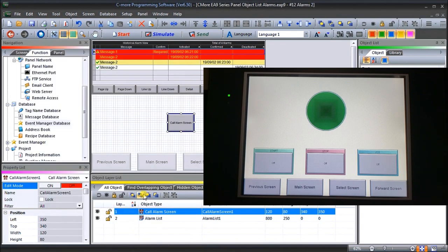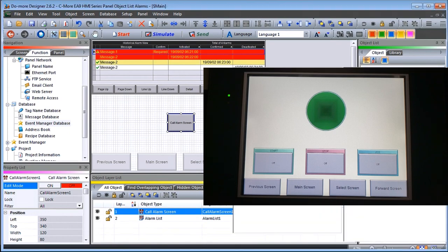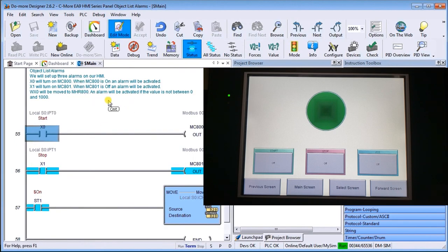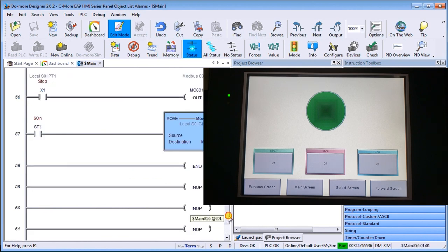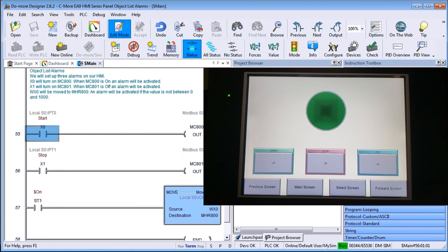Now our display is all powered up and ready to go. We'll call up our simulation for our PLC. In Do More Designer, to simulate our events: when X0 turns on, MC800 turns on which activates the alarm; when X1 is off or stops, MC801 alarm activates — so MC800 acts when it turns on, MC801 acts when it turns off. Then we have an always-on contact which moves WX0 into MHR800 — currently at about 828. That is our entire program to operate these three alarms.